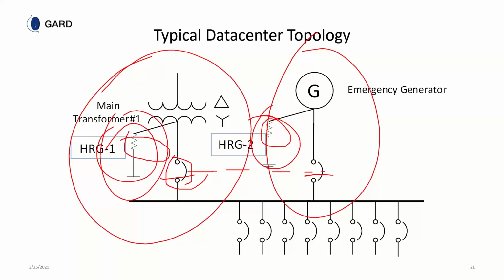So the utility breaker is open, the generator breaker is closed. And I think because you're on generator, this makes it now extremely crucial that you must have monitoring on the generator. So I don't think you can differentiate between normal and generator. If you have a resistance ground in the system, I think the Canadian Electrical Code says you have to monitor both.